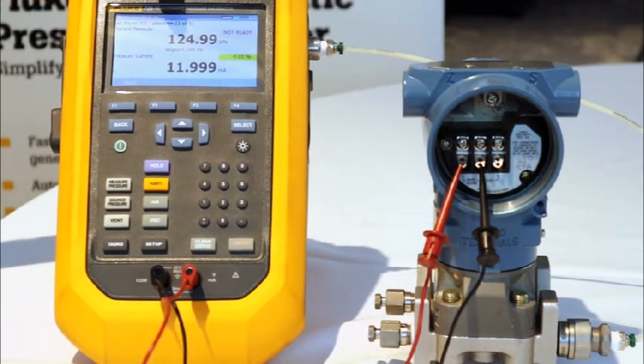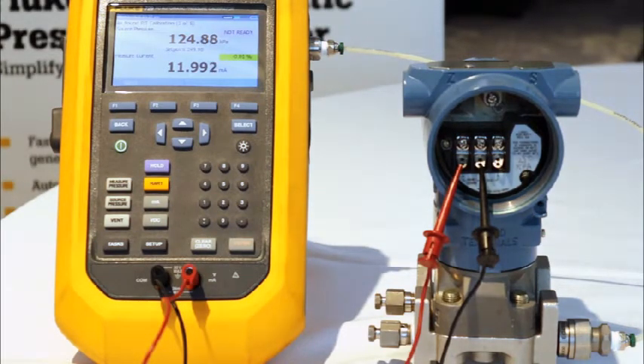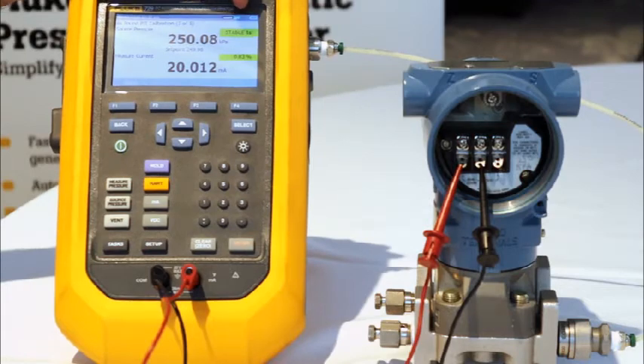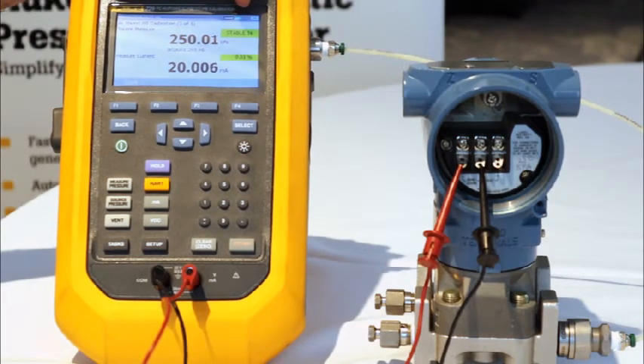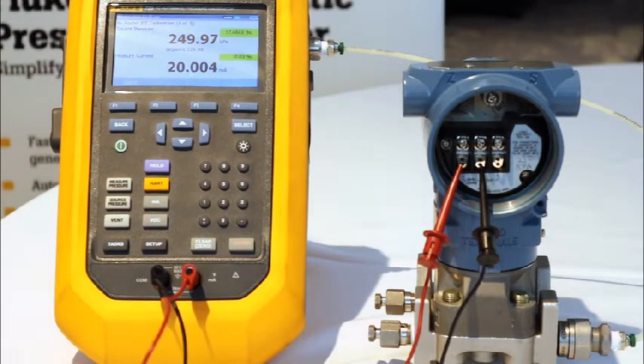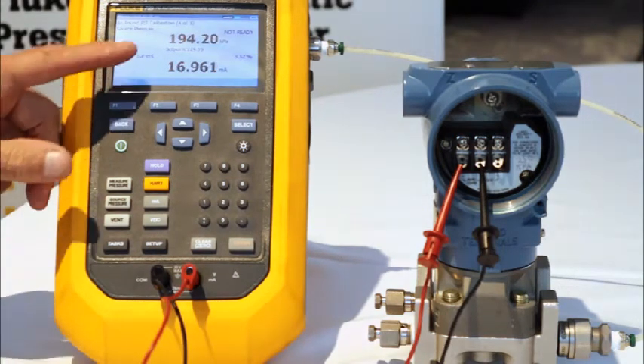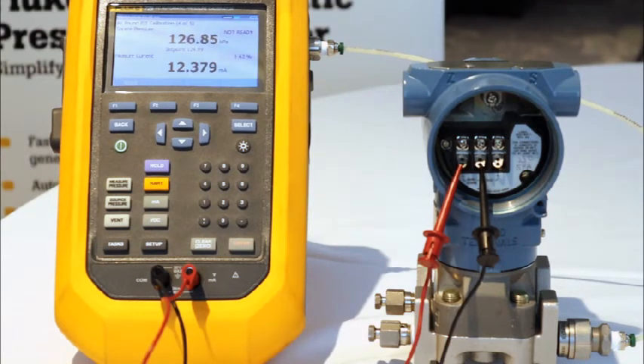Stable for 5 seconds. Now we go to the full scale. Okay. We're stable at full scale for 5 seconds, and then we'll start the descending test. Next set point, we're going to drop down to 125 kPa. And then back to the starting point for the documented test.